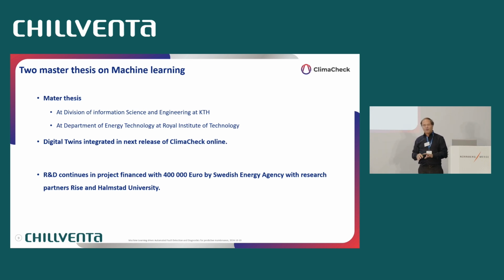Then with the basis of energy signatures and performance analytics, we have started to implement machine learning, and that is really going to be a game changer, because if you look at compressor efficiency, for example, that is changing. So if I have a slide regulated screw, maybe the compressor efficiency is 30% at part load, and it's 72% at peak performance. So to set up the alerts for that, you would have to take into consideration different load conditions to be able to detect with a good accuracy. But if you have a digital twin of a slide regulated screw compressor, then you only need to say that I allow X% deviation. So it saves a lot of time and it increases the accuracy drastically.